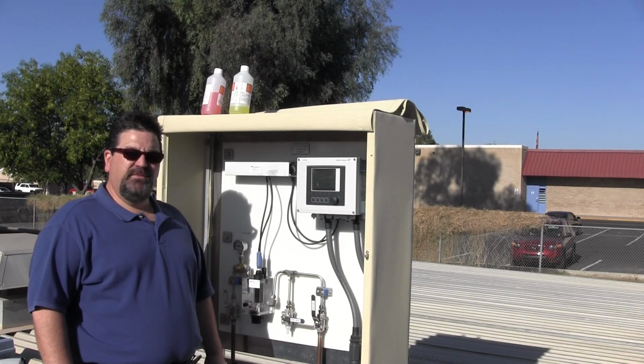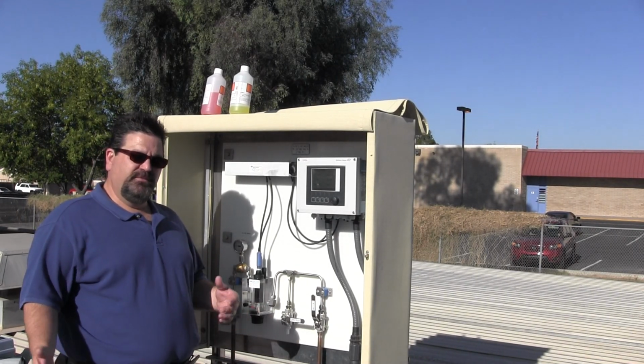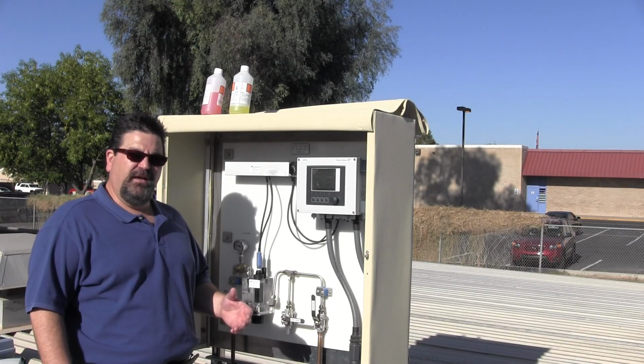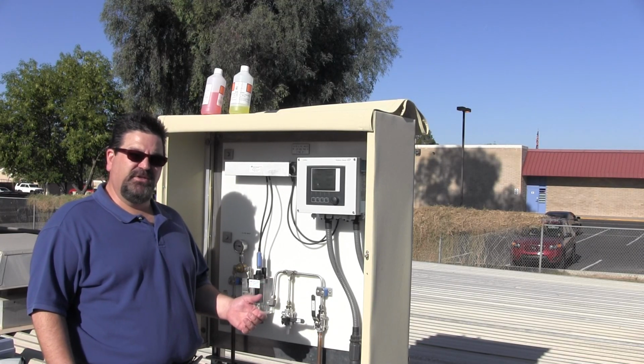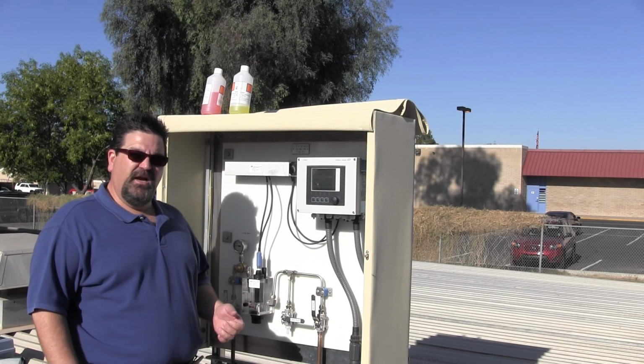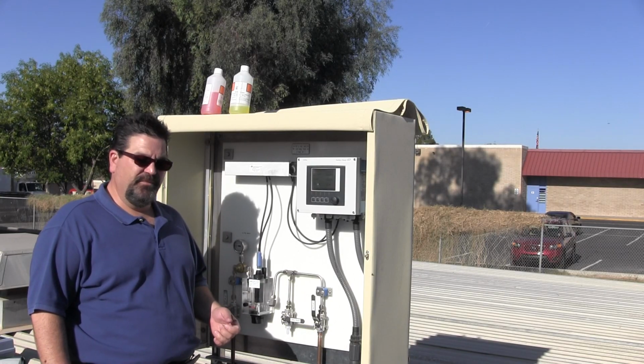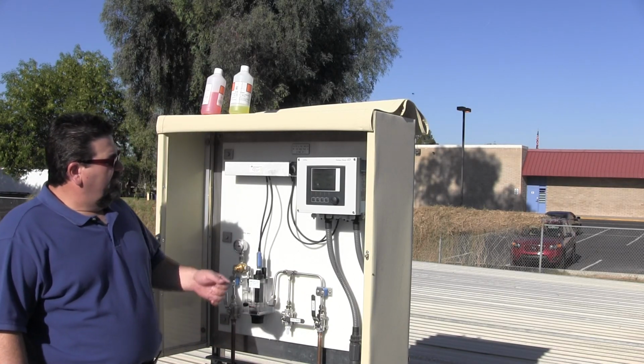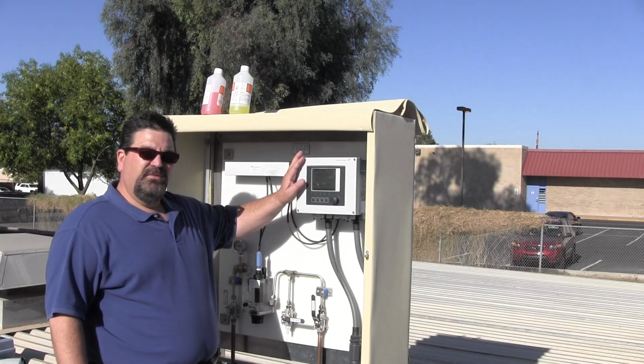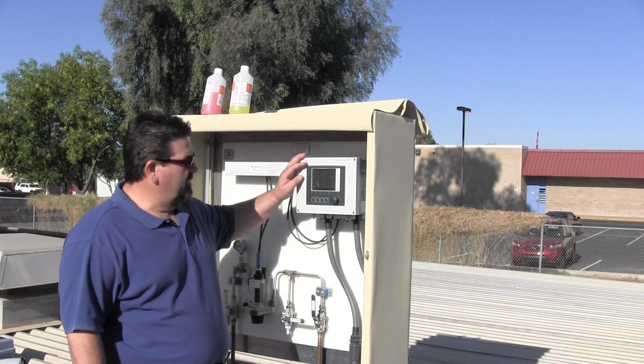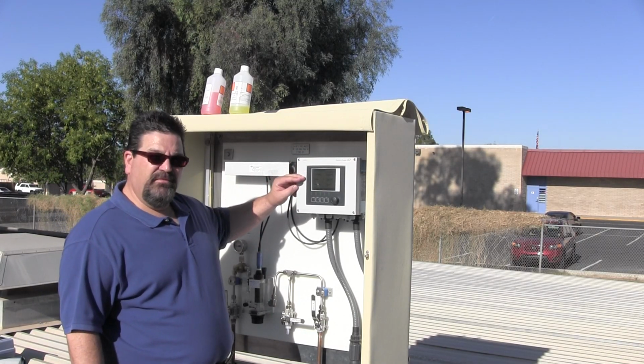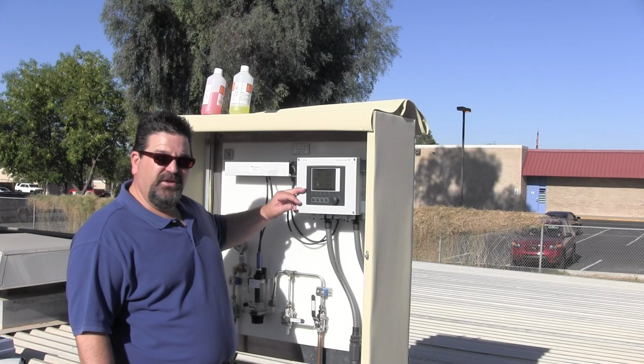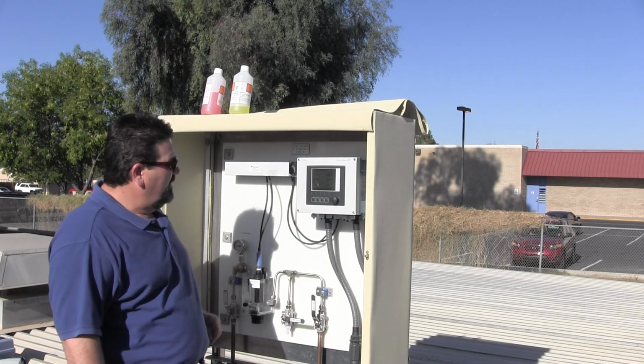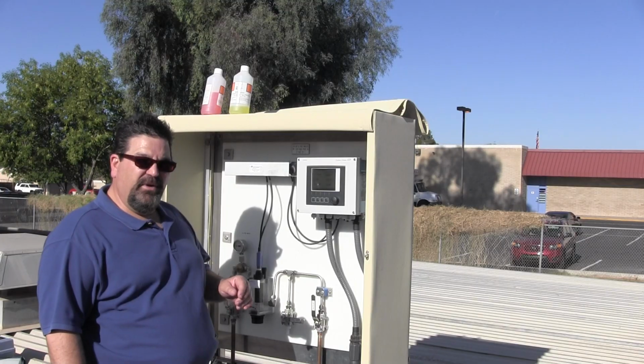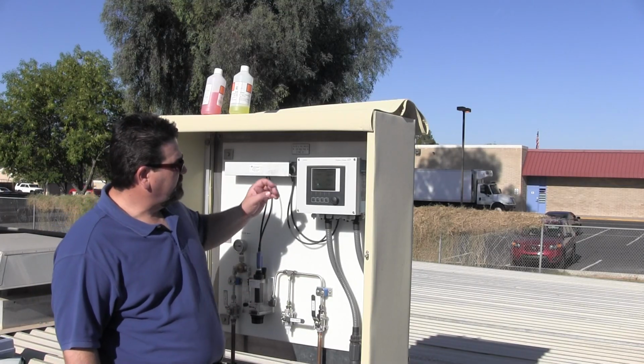The second calibration method that you will need to somewhat routinely perform on the analyzer is calibration of the pH electrode. We want to spend a few minutes documenting that process here for you. Again, we're going to see the normal screen of the transmitter. Top line chlorine value, middle line pH value, bottom line temperature. The steps to get through this calibration process are slightly different.